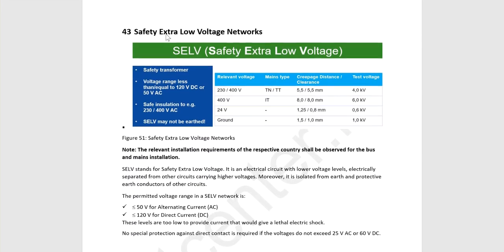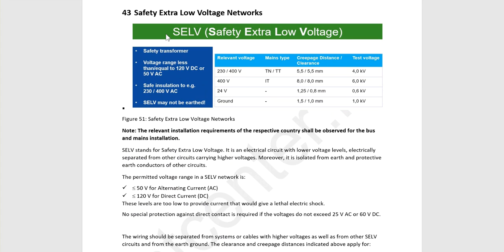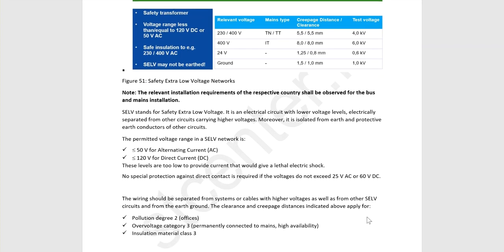First of all, the book said that the KNX network is SELV. So what is SELV? It's a safety extra low voltage network. The permitted voltage range for a SELV network for AC is below 50 volts and for DC is below 120 volts. And it is said that no special protection against direct contact is required if the voltage does not exceed 25 volts AC or 60 volts DC. So this is totally safe for human beings, this type of voltage.